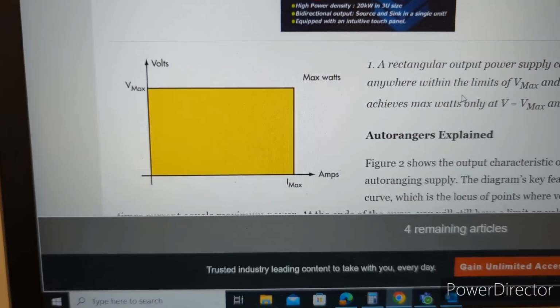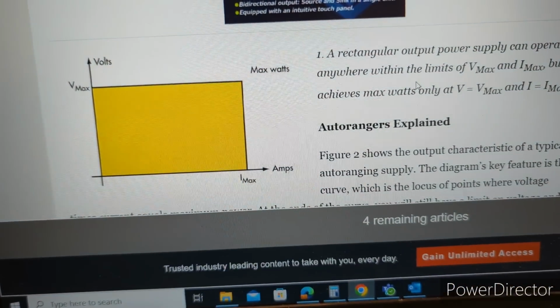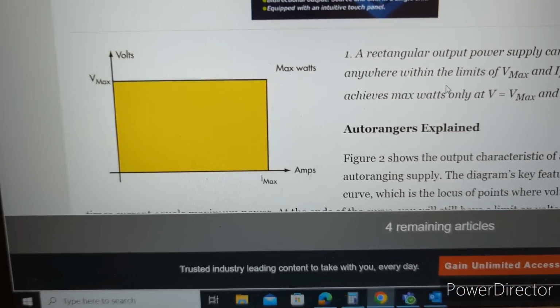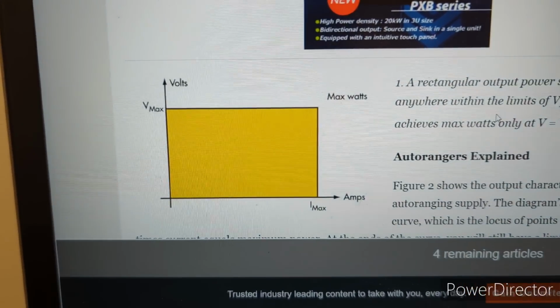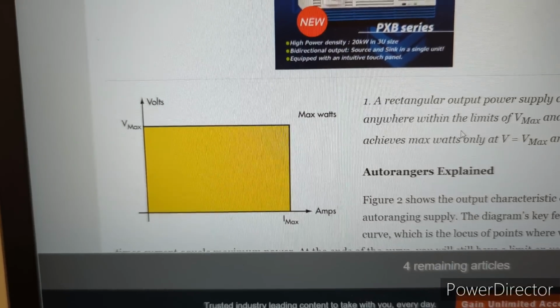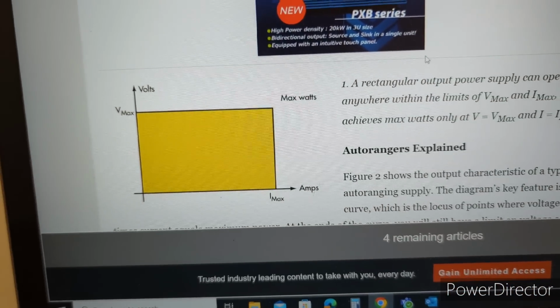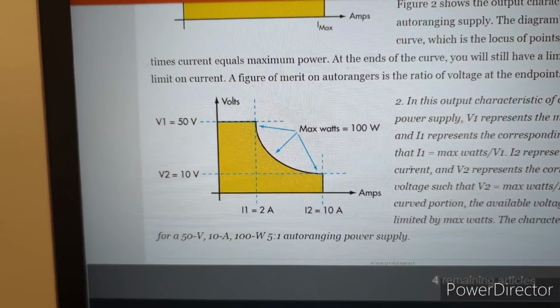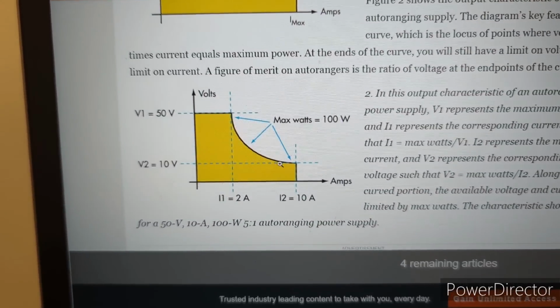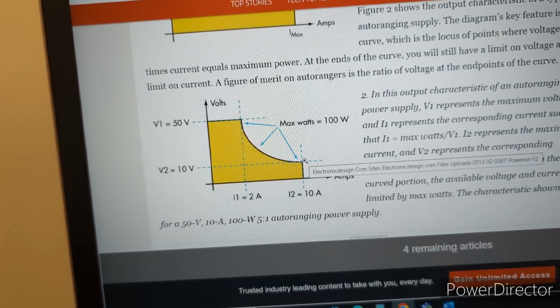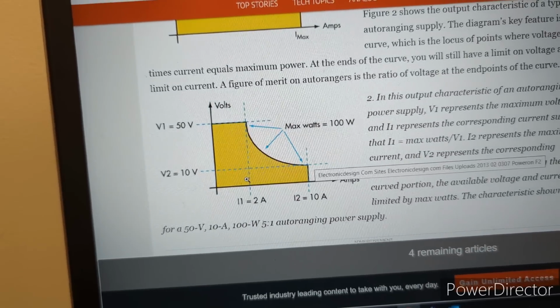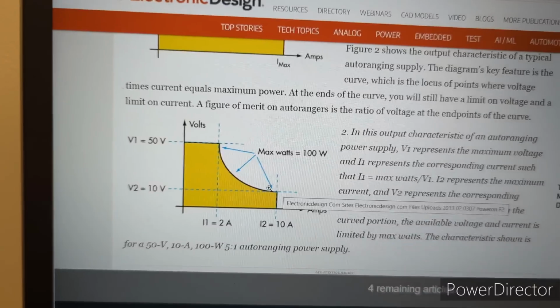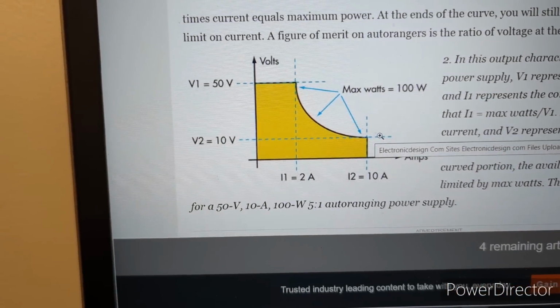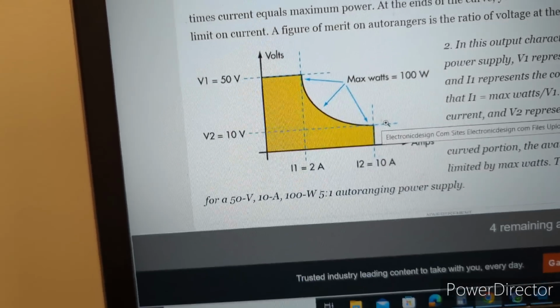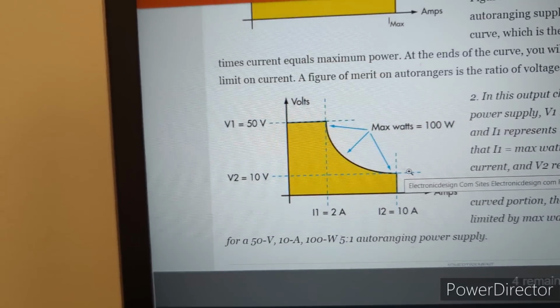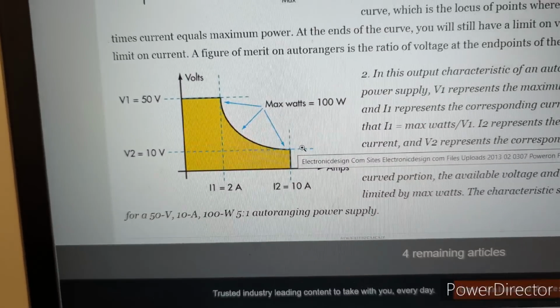Here you can see that a regular power supply has this rectangular representation. So at max volts, max current, you just multiply them together and you have your max watts. Now with an auto-ranging power supply, the graphical representation is a bit different. The slope of this line is the max output that you can achieve for the power supply as you're adjusting the settings. They use in this example a 50 volt max supply, max 10 amps, and max watts is 100.